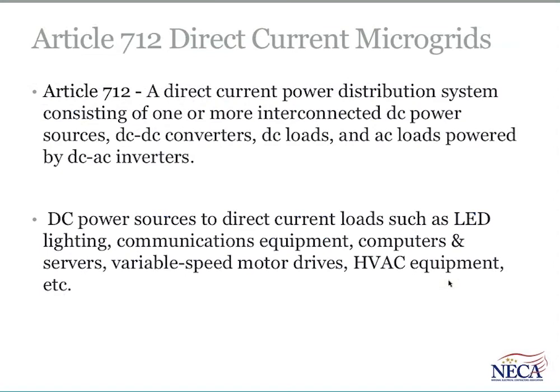In Article 712, we talked about in Part 1 when we mentioned the new articles, direct current microgrids, a brand new article. It's a distribution system consisting of one or more power sources, usually a wind system and a PV system, connected in conjunction with the utility and controllable by a customer to dial in the amount of renewable energy system use that's taking place as compared to whether you're using the full utility capacity. So we're going to see a lot more common use of these grids, and they're very small. Some of them are very small within buildings. Some of them could be at the neighborhood level size, campus level size, and so forth. Microgrids is a common location where you'll see energy storage systems applied as well.